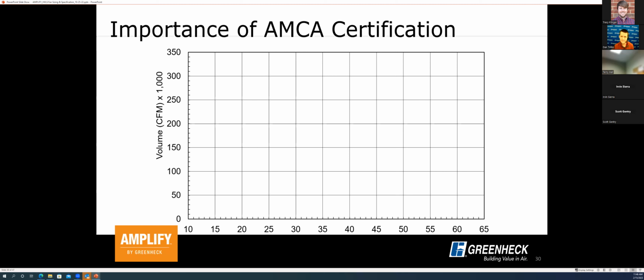So there are products out there still advertising or promoting some of that inaccurate performance data. What we've seen is that there are pretty large discrepancies between that advertised, historical data and the actual as-tested data according to the AMCA standard. In many cases, it's upwards of about 30 to 35% lower actual performance than what the manufacturer is advertising. That's why AMCA certification is so critical for this type of product.